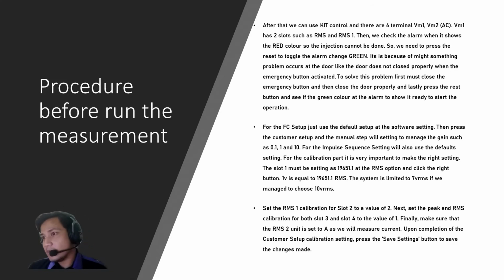For the impulse sequence setting, we'll also use the default setting. For the calibration part, it is very important to make the right setting. The slot 1 must be set as 19651.1 at the RMS option and click the right button. 1 volt is equal to 19651.1 for the RMS option. The system is limited to 7 VRMS if we manage to choose 10 VRMS.